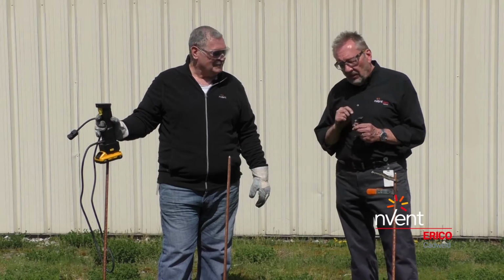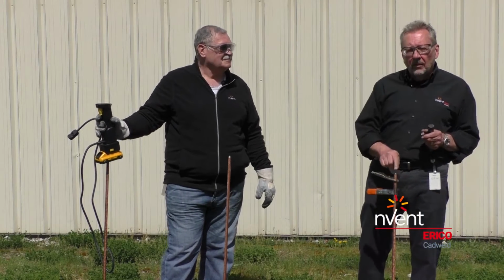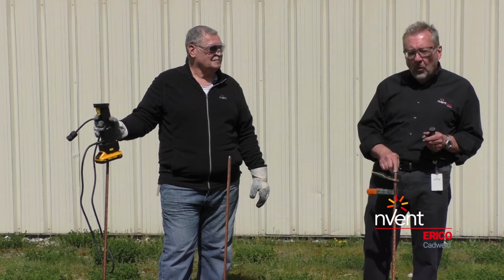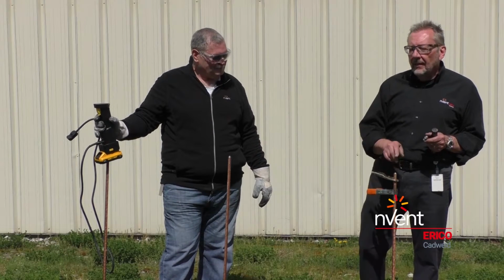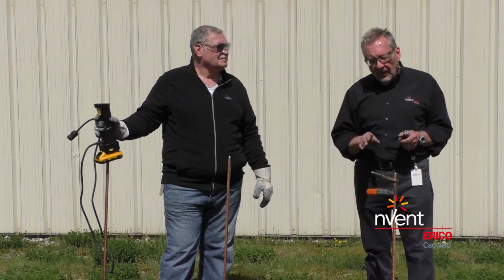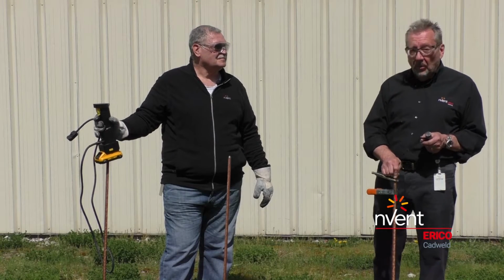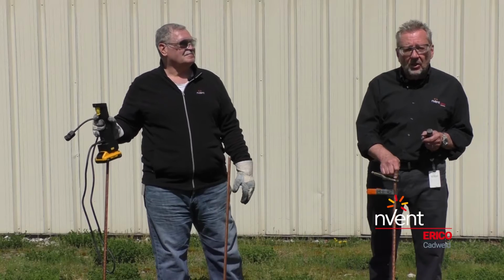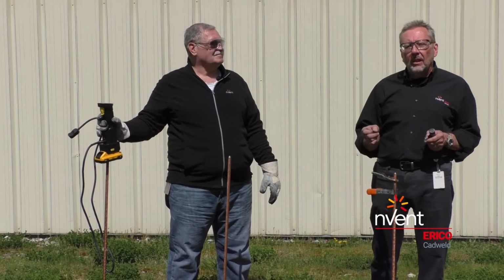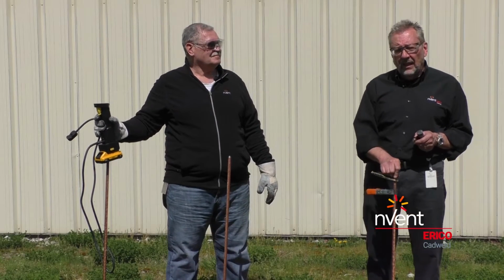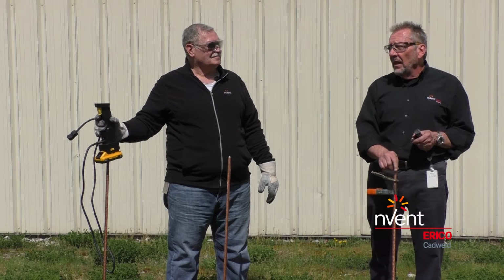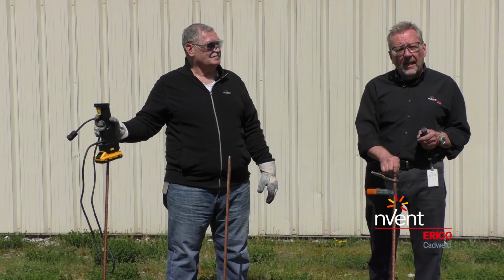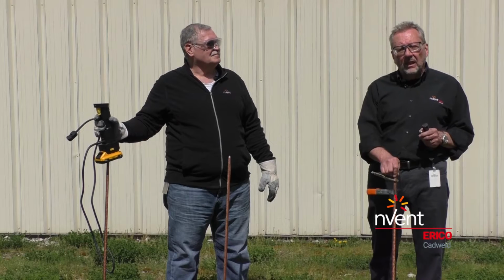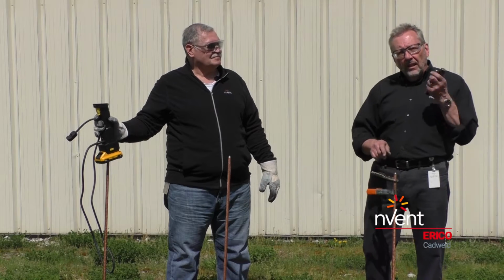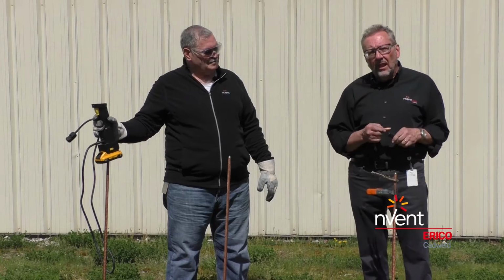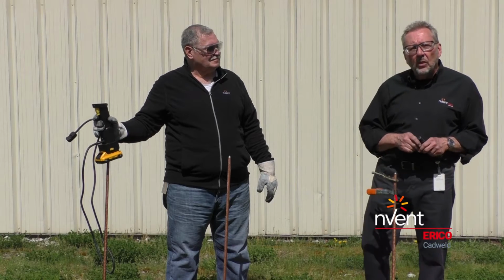Good thing you asked. It's very important when driving these rods that we don't deform the top of the ground rod. That matters whether we're making an exothermic connection—where it's critical to have the top of the rod in good shape—or even just putting an acorn clamp on the rod. If you've mushroomed the top, you'll never get even a mechanical connector on it. So it's important to protect the top of the rod while driving it.